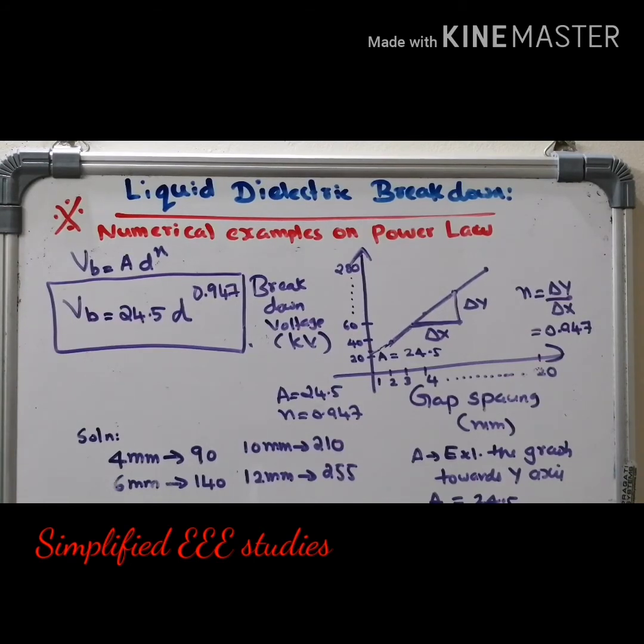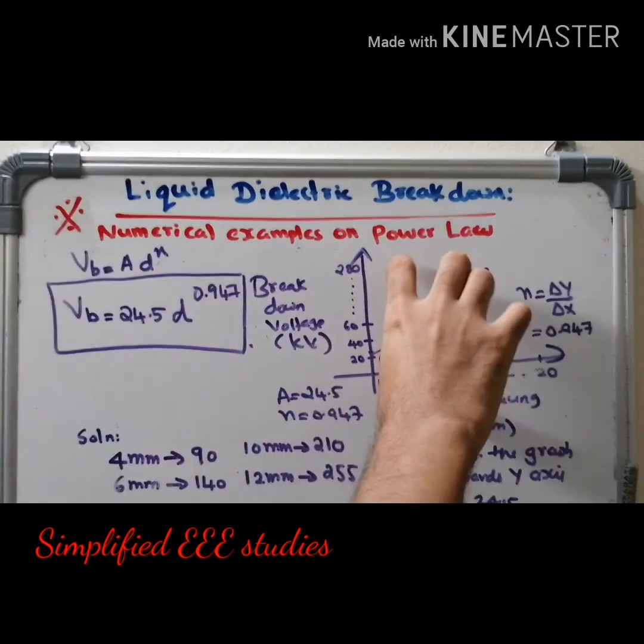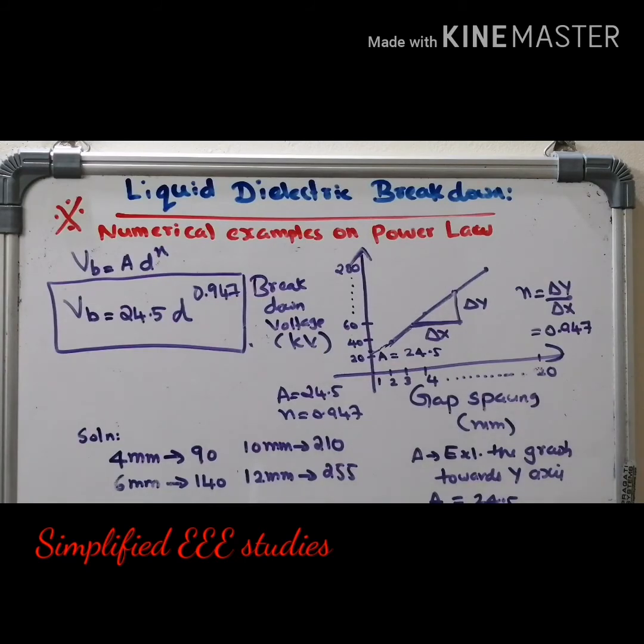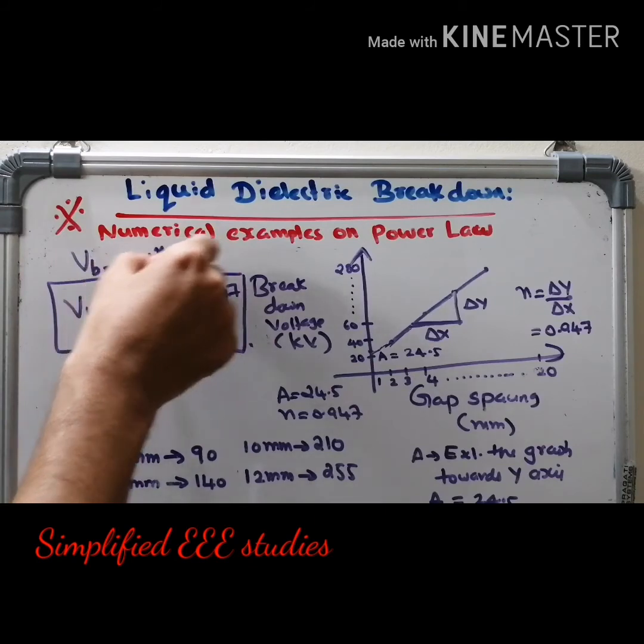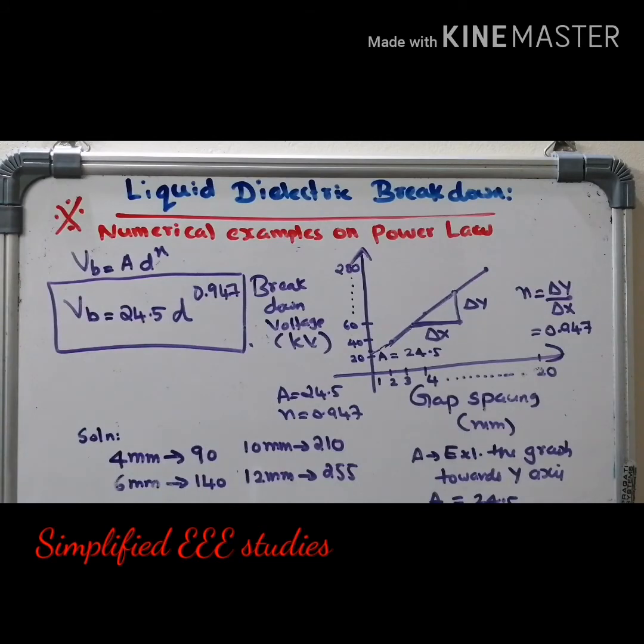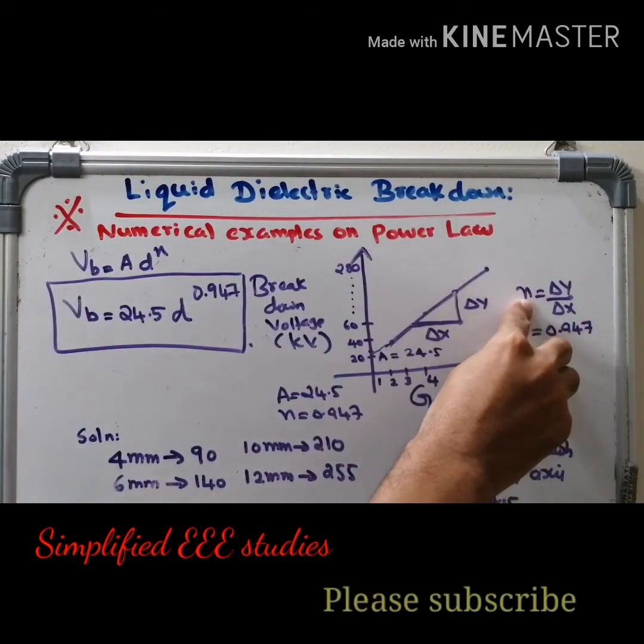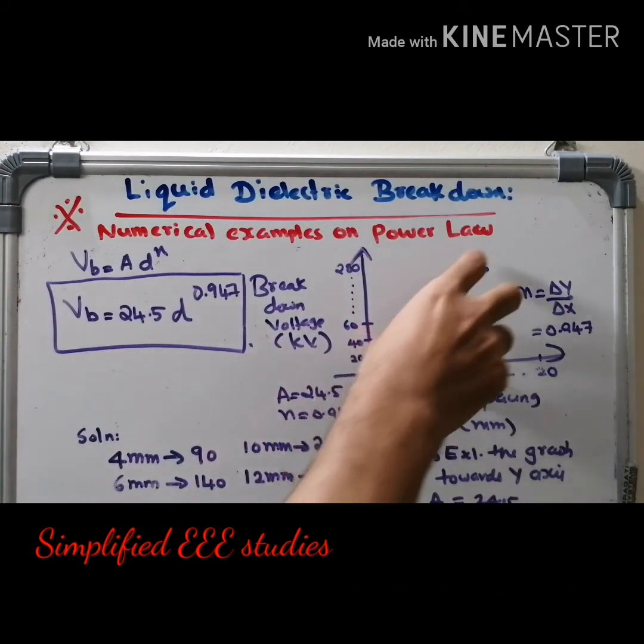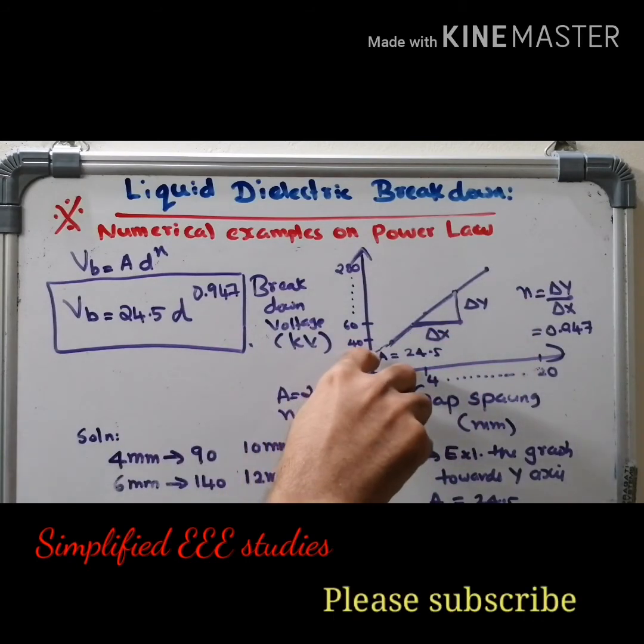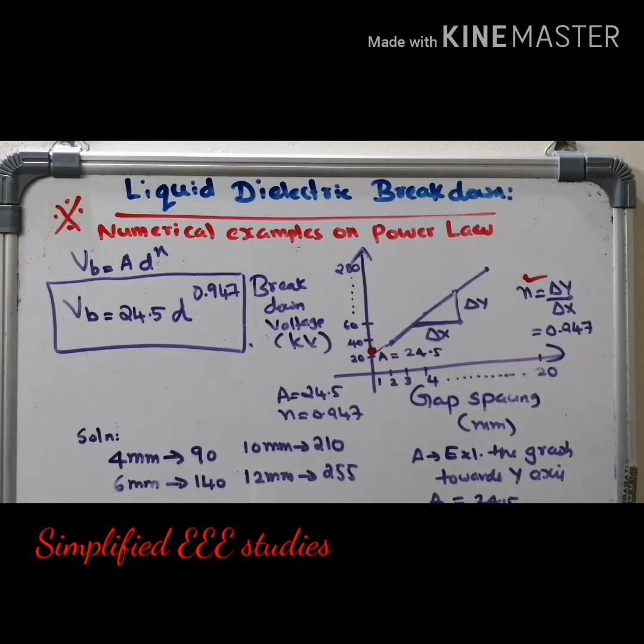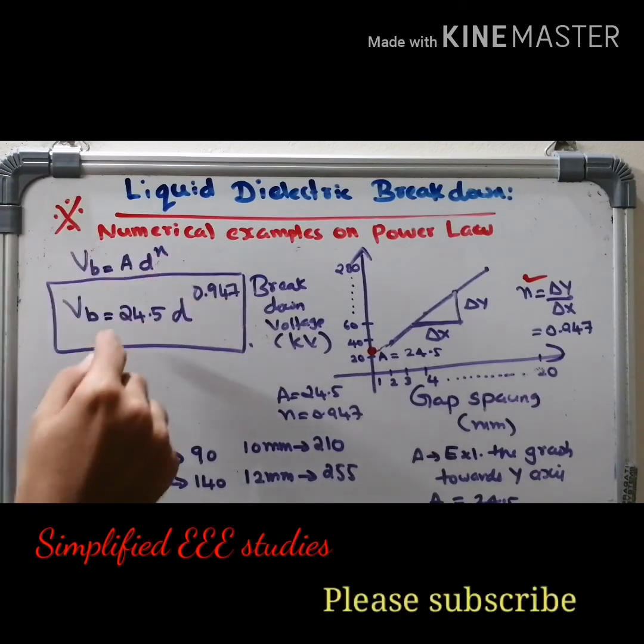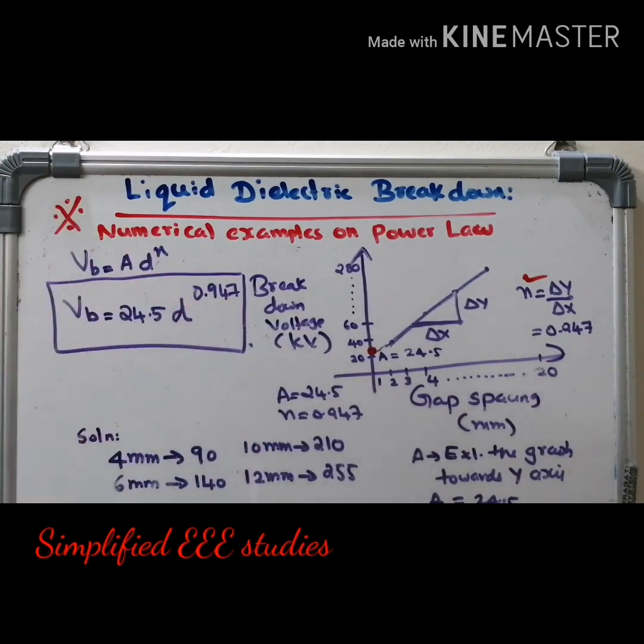Let me conclude. First, read the given data and segregate it. Next, plot the graph — breakdown voltage on Y-axis, gap spacing on X-axis — and you will get a straight line. Then derive the expression: VB = A · D^N. Calculate slope N from the curve. Thereafter, extend the curve towards the Y-axis; the meeting point gives A. Put the values of A and N into the equation to obtain the final power law.